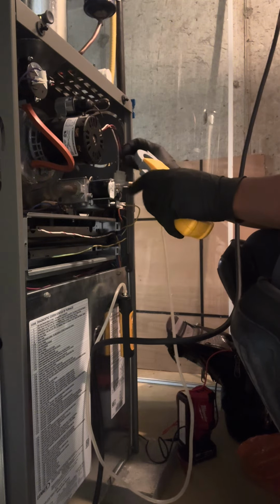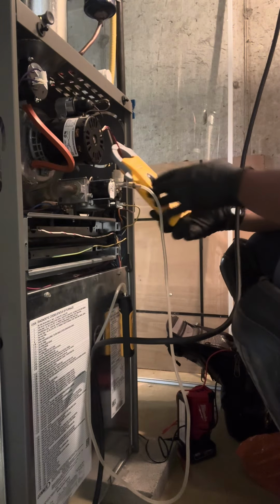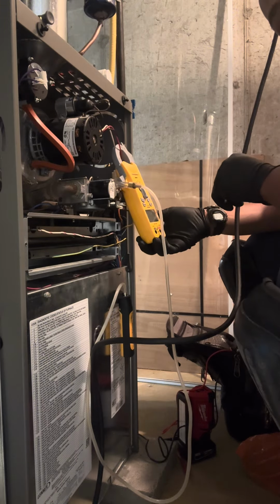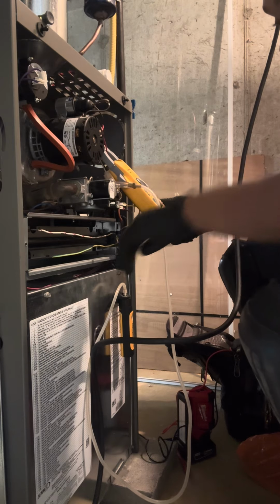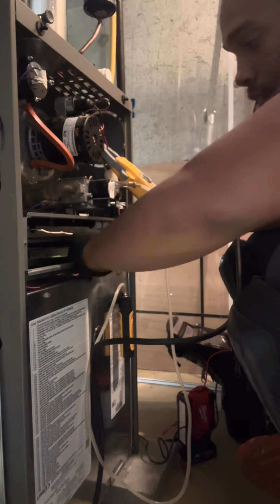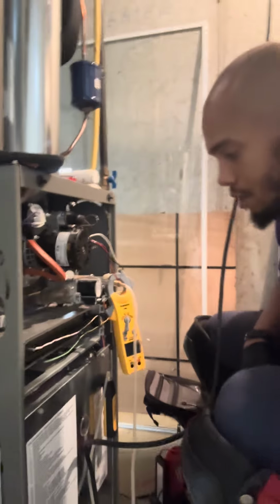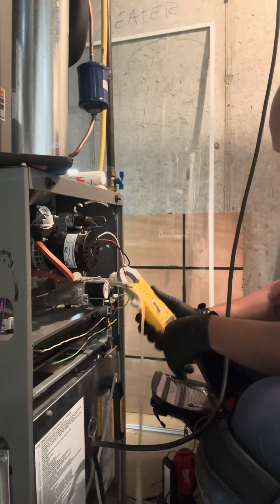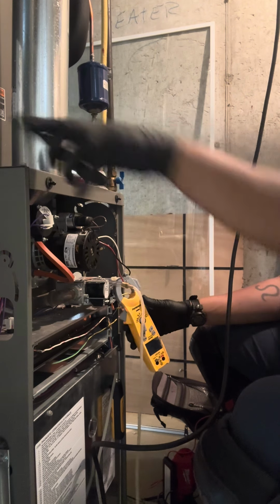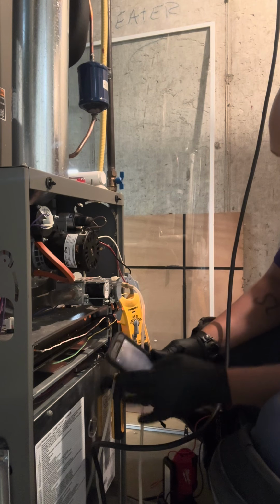Multimeter. I want to start off on the low side of the inducer motor. I want to see that inducer motor's amperage. Then I'm going to switch to the high voltage wire, and I'm going to test the blower motor's amperage. All right, the system just started up. So we're going to test and see what we have. Our hot surface igniter is kicking on. As you can see, that thing is glowing.